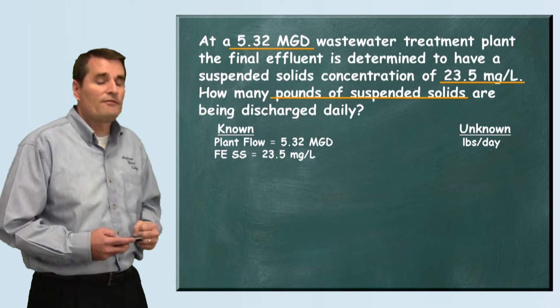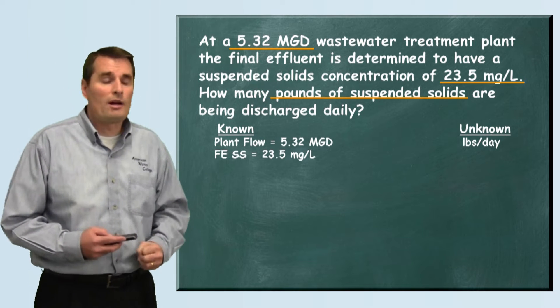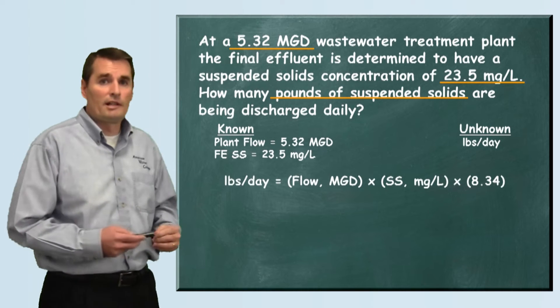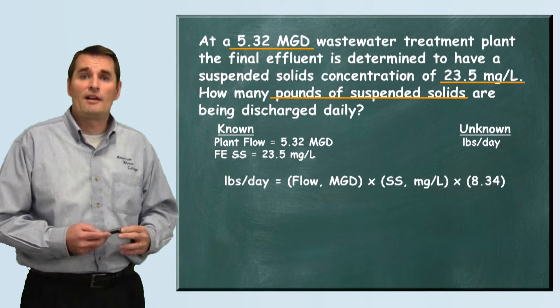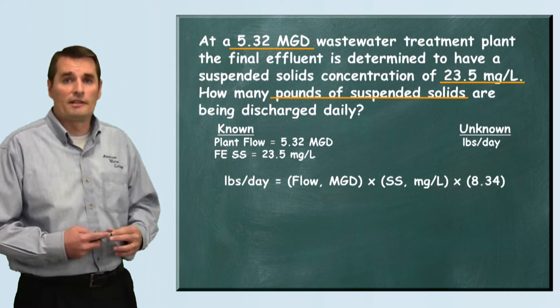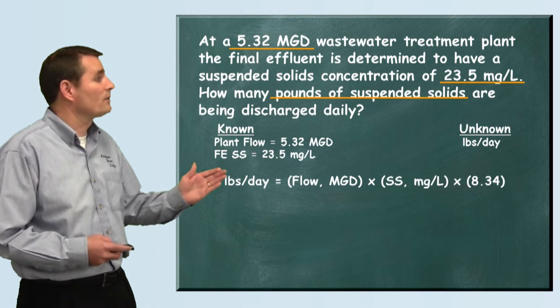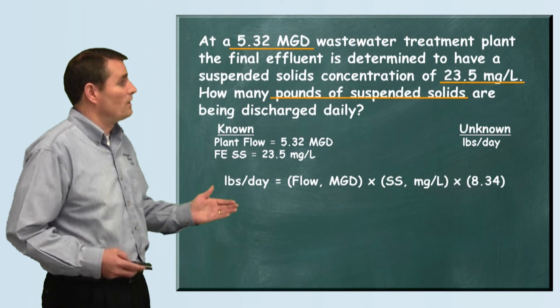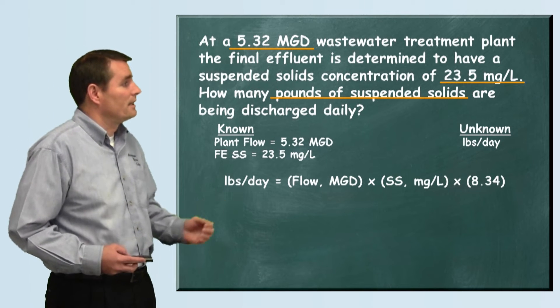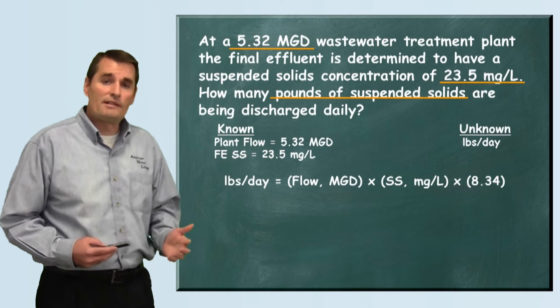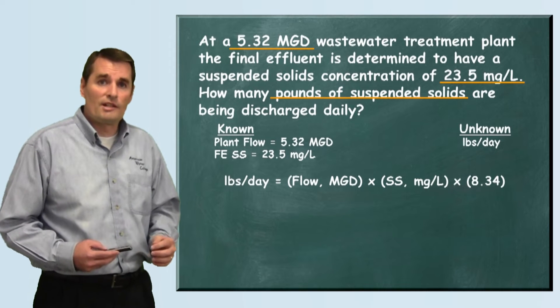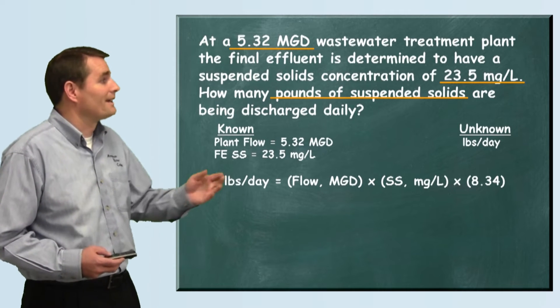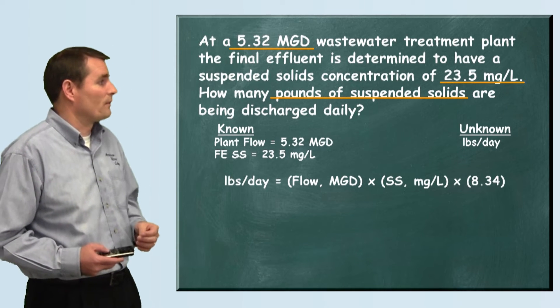Now that we've pulled that information out of the problem, we want to select our formula. It's the pounds per day formula: pounds per day equals flow in MGD times the suspended solids concentration in milligrams per liter times 8.34.